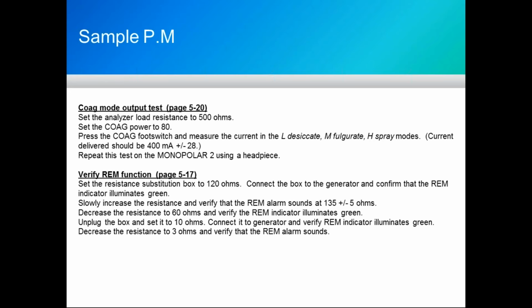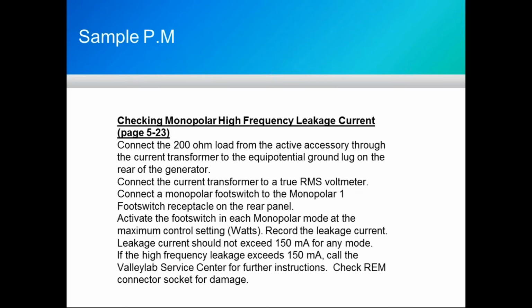You set it at 120, make sure it goes green, and slowly increase it, and when the alarm sounds at 135 plus or minus 5 ohms, then you continue through the test. That will verify the REM circuit, which some people also know as the patient plate. Then we're going to go through the checking of the monopolar high frequency current. You connect a 200 ohm active accessory through the transformer. Then you connect the monopolar foot switch on monopolar 1.